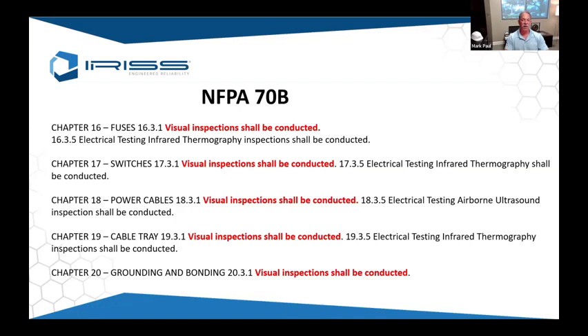You may have had some condition that wasn't an issue with the electrical system, but maybe something happened that triggered that sensor to give you an alarm. If you had the perfect combination of Safe Connect clips, IRISS inspection windows, and a high-tech IoT system giving feedback, you could get this alarm trigger, then go to the asset, open the inspection window, and visually see if the thermochromic clips changed color, or the paint applied to the bus bar had changed color. Then you have double assurance that if you shut the equipment down, it's for a good reason, not just because the sensor was faulty. So you're getting duplicated confirmation that you're making a good decision by taking this equipment out of service.